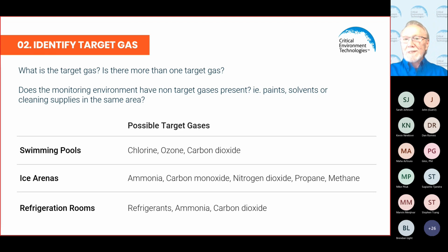So these are some of the different things that I've seen in regards to the use of high concentrations of carbon dioxide inside building envelopes, and knowing that carbon dioxide is a very dangerous asphyxiant gas in pretty much all of North America now. There are rules and regulations in regards to wherever there's a carbon dioxide cylinder or some type of use inside a building envelope, there must be a carbon dioxide detector and audible visual notification appliances if that carbon dioxide leaks and starts to build up in that building envelope.